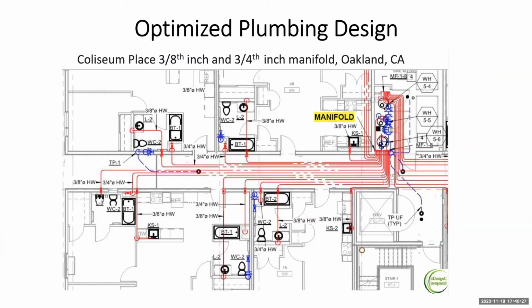So anyway, these are 3/8-inch pipes that you're seeing. They're from a manifold, so there isn't a recirculation system. Everything here is within 50 feet, which we calculated so people could get their hot water in like 5 to 15 seconds. This is the most efficient way you could do it, and it's very similar to what Pete Skinner is doing.